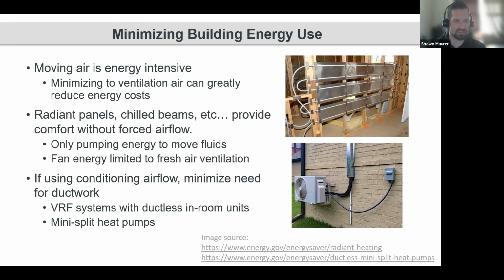If you're using conditioned airflow, minimize the need for ductwork. Using things like VRF systems where you've got primarily refrigerant piping, but the unit is just recirculating air in that space. It might have a dedicated outdoor air system ducted to it where it's also conditioning the outside air a little bit. But mini split heat pumps and VRF systems are an excellent way to minimize that airflow to just what you need for ventilation, and your space conditioning is provided by a much smaller fan within the space itself.